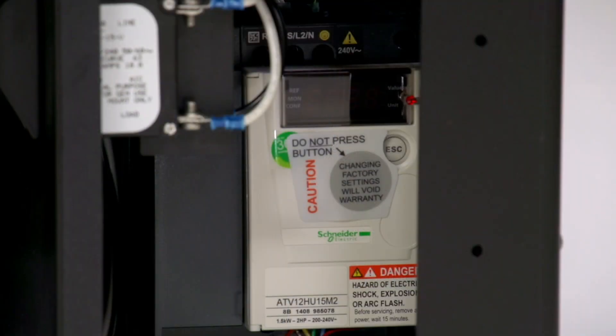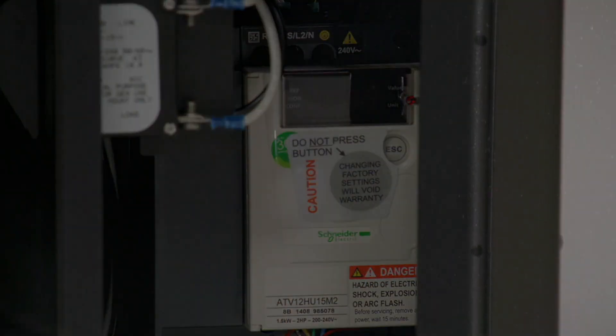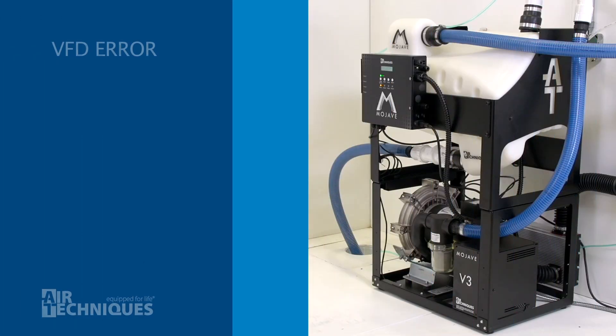Reset the VFD by shutting off the main circuit breaker and waiting three minutes until the VFD completely resets, then turn the breaker back on. Always wait the full three minutes for the VFD to reset. There are capacitors that keep it powered even after the power is off.